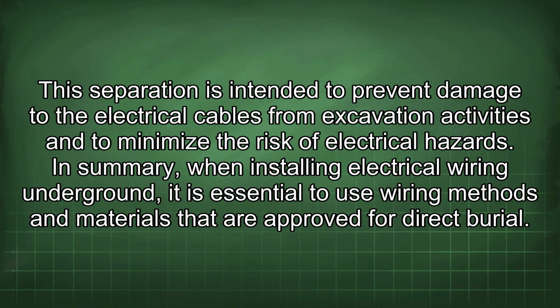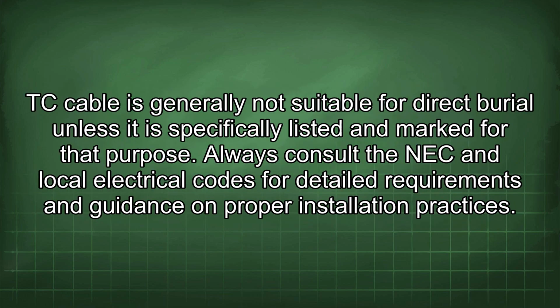In summary, when installing electrical wiring underground, it is essential to use wiring methods and materials that are approved for direct burial. TC cable is generally not suitable for direct burial unless it is specifically listed and marked for that purpose.